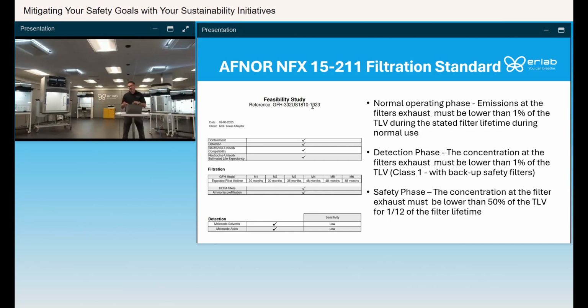filters. And then we have the detection phase, and that's where the solvent sensor or acid sensor in that fan box comes into play. And that is where it's constantly sampling the air. If, say, there was a spill in the hood, you spill a beaker of acetone, temporarily overwhelms that main carbon filter, that solvent sensor will alarm. But by having those backup carbon filters on top of the fan box that add that added safety redundancy, we still guarantee no more than 1% of the TLV will be released past that backup filter. And that's why the backup filters are so important. And then the safety phase would be if you were to have the breakthrough alarm continuing to go off, you ignore it, you have about 1/12 of the filter lifetime to change the filters, and you'll be at 50% of TLV or lower.